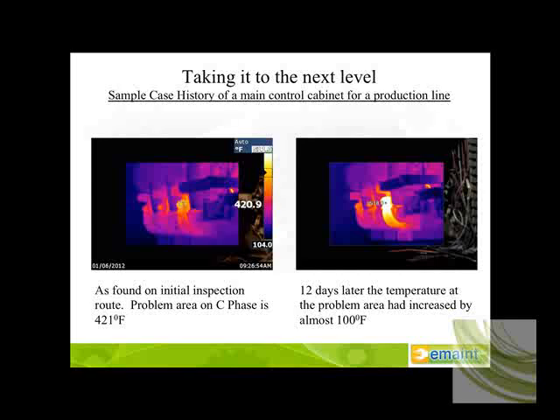On the initial inspection, the C phase of this particular contactor block was exhibiting a temperature of 421 degrees Fahrenheit on the C phase here, the right-hand side. You can see the little box gives you a temperature measurement output there. The image on the right shows another inspection conducted 12 days later, and already there was a 100-degree Fahrenheit rise on that same hotspot.